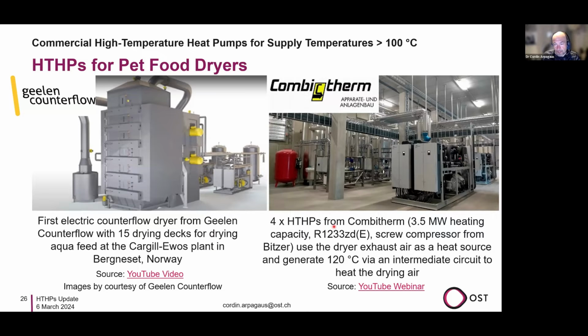They are using here four high temperature heat pumps from Combitherm, 3.5 megawatt heating capacity. They use R1233ZD as a refrigerant, and screw compressors from the company Bitzer, which allow this high temperature compression. Then, using intermediate circuits, this heat is brought into the dryer.